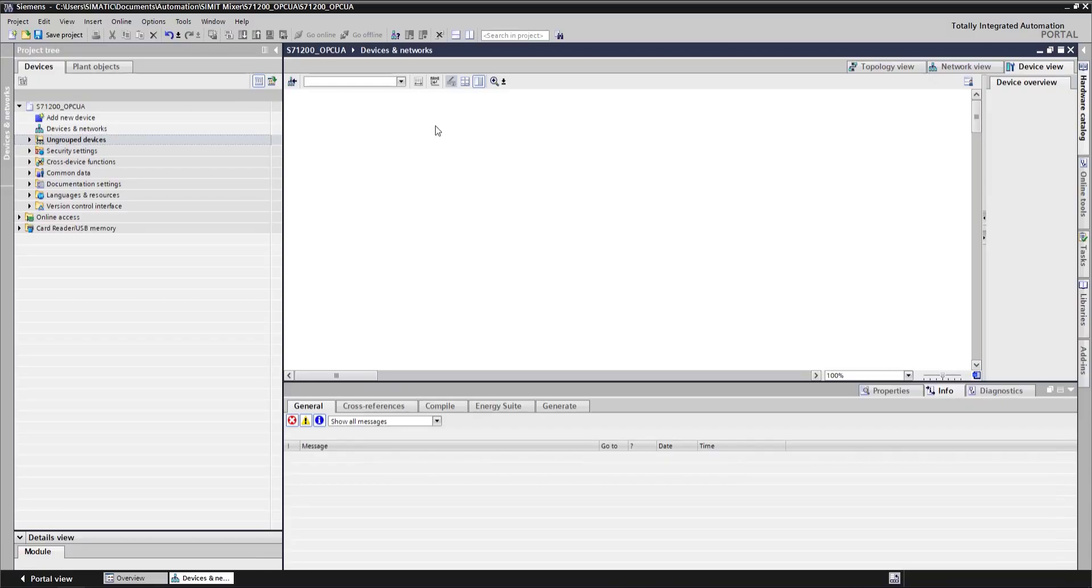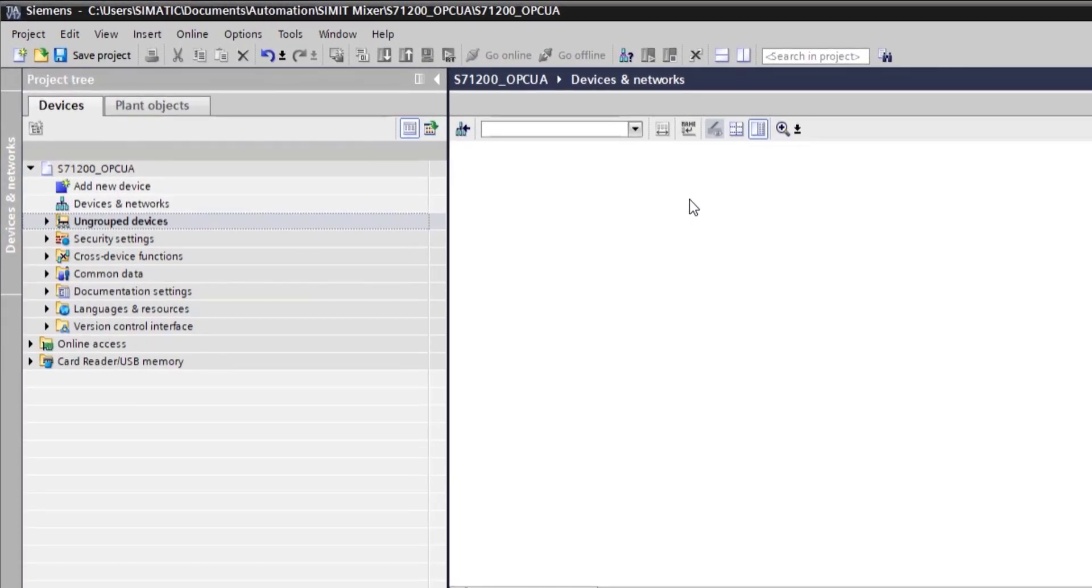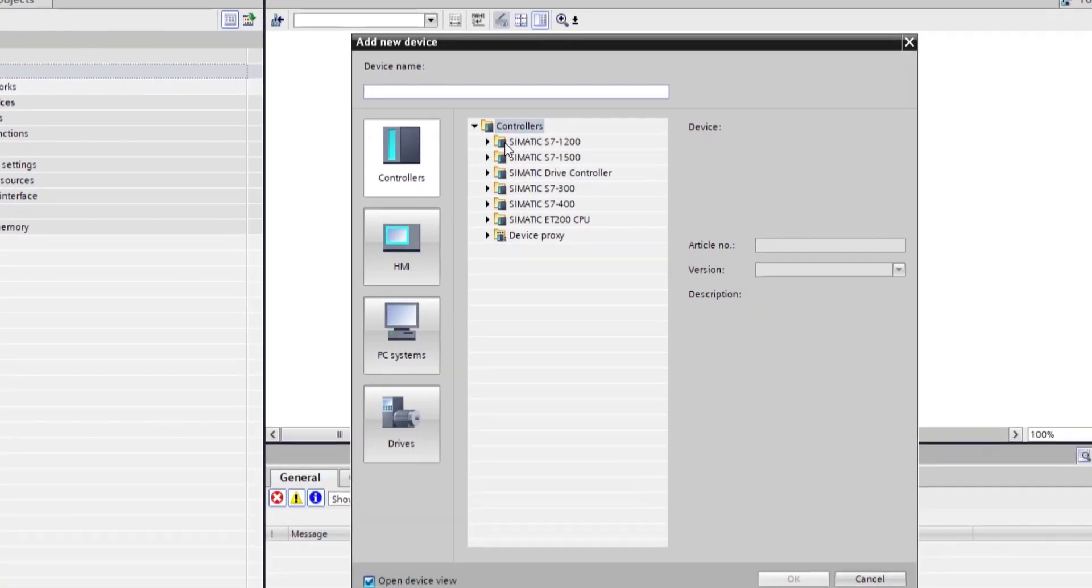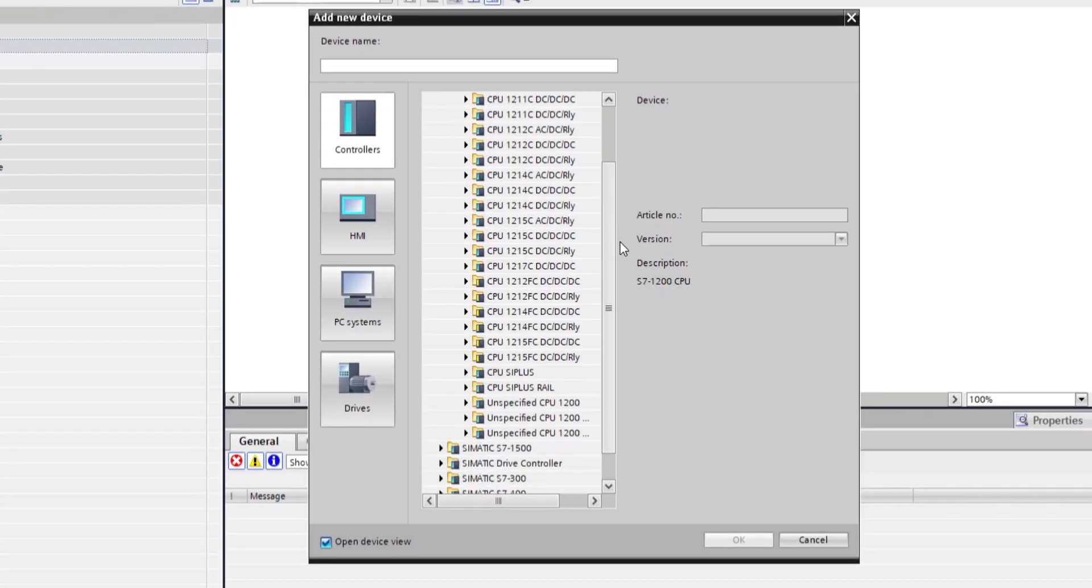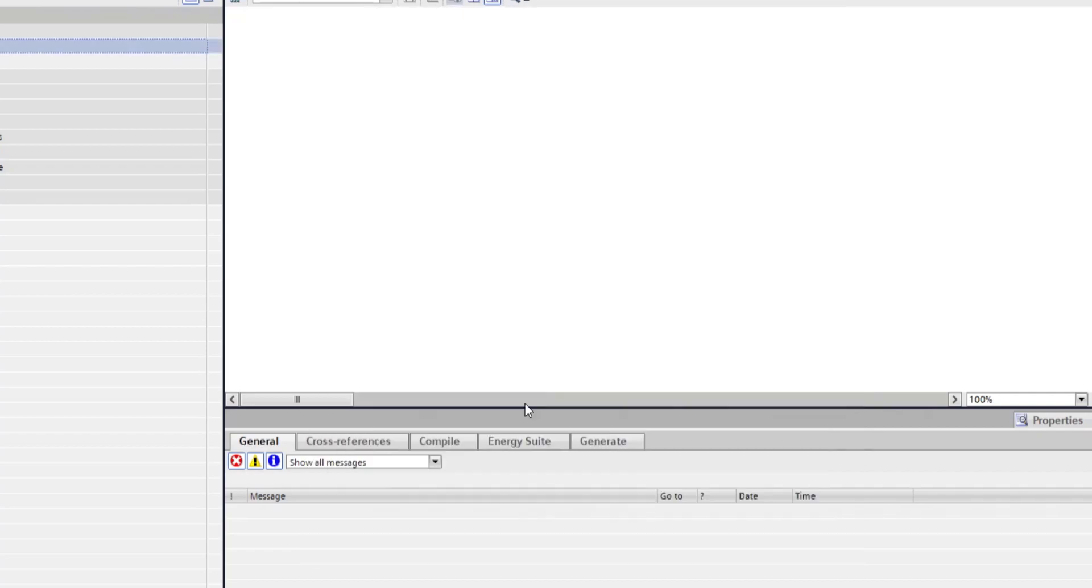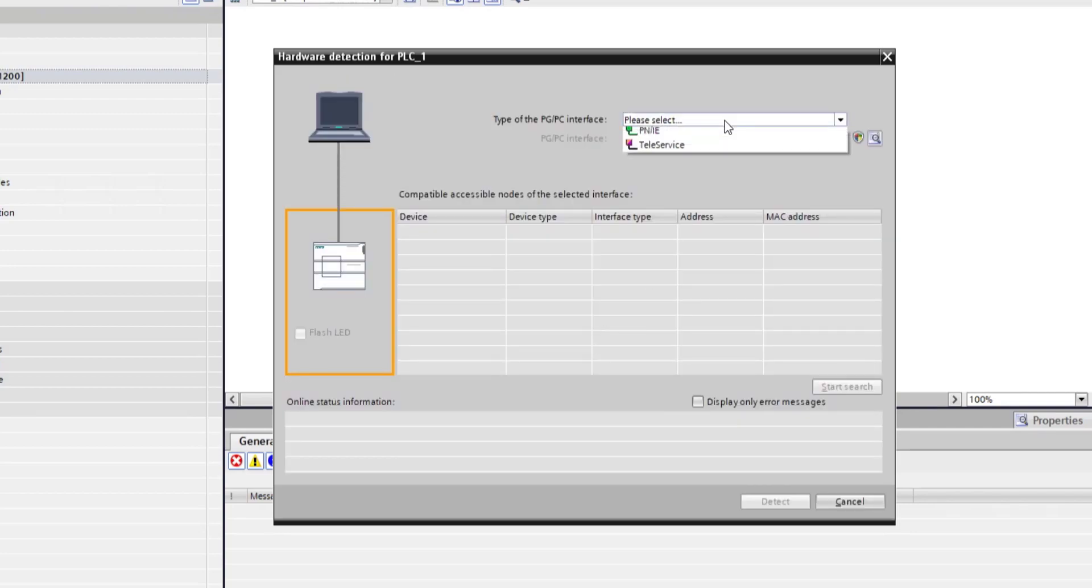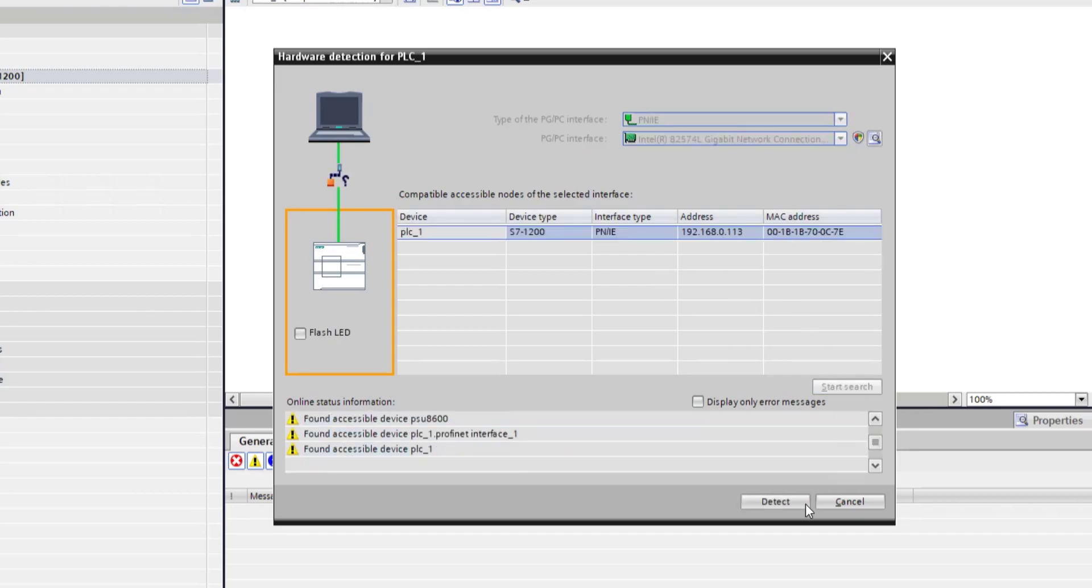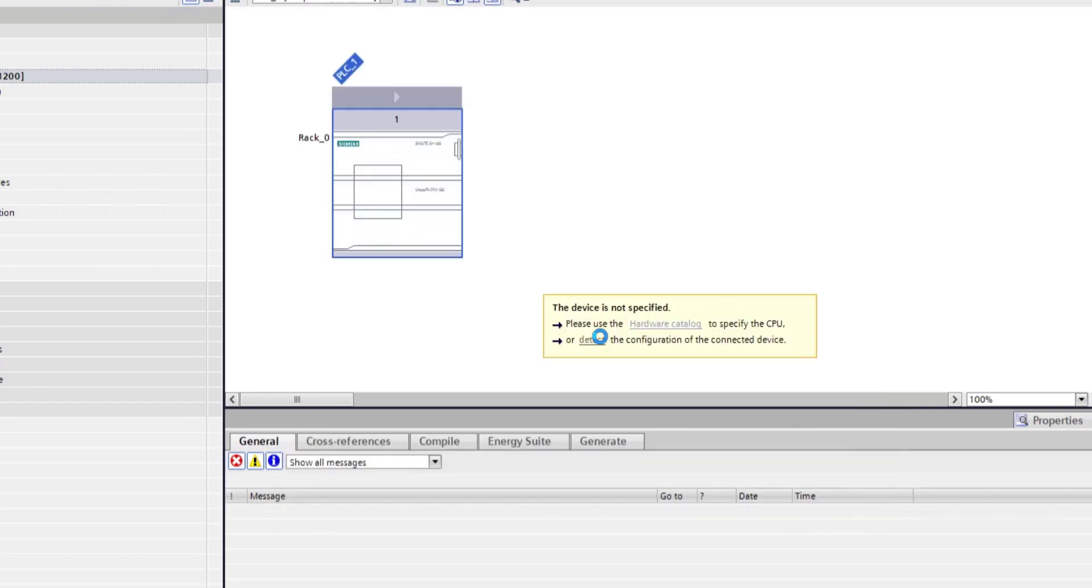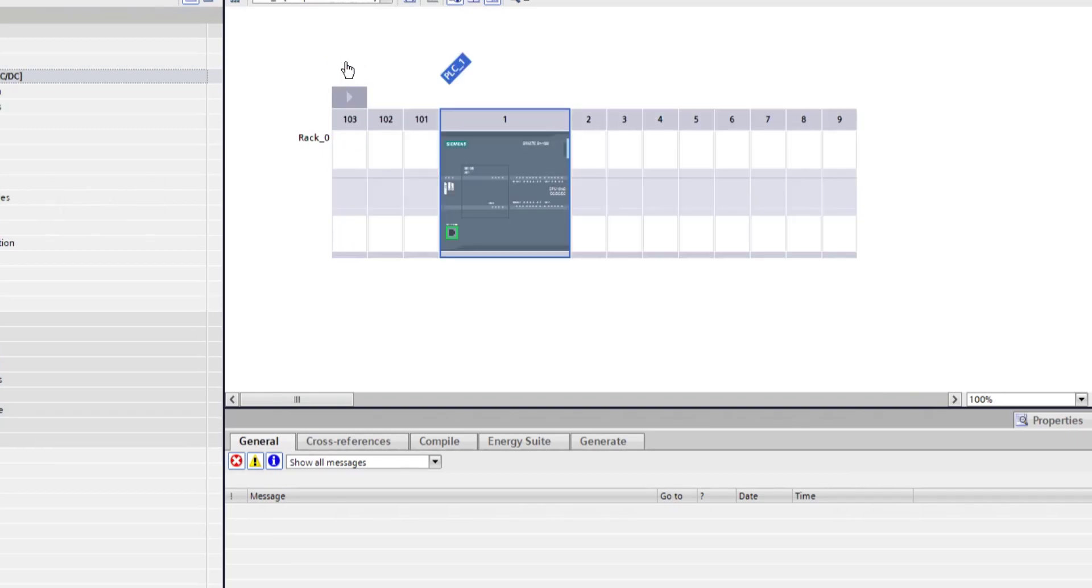I have a fresh new project. I called it S7-1200 OPC UA. Let's add a device. Now I know that I have a 1200 CPU but I'm not sure which one it is. So I'm going to be using the unspecified CPU option and I will detect it on my interface. So I'm using the TIA Portal functionality that allows me to detect devices and configure the hardware accordingly to what's there in real life. So there you go. We detected our 1200 on 0.113 IP address.